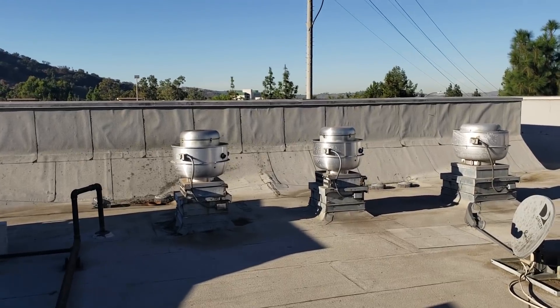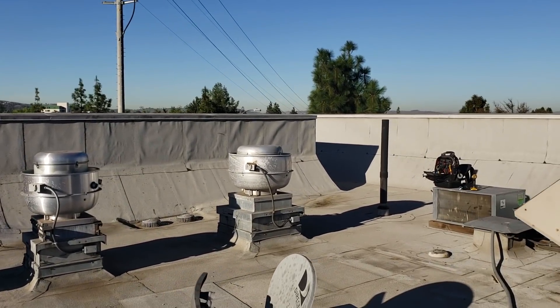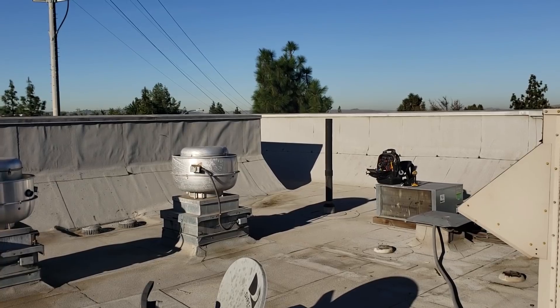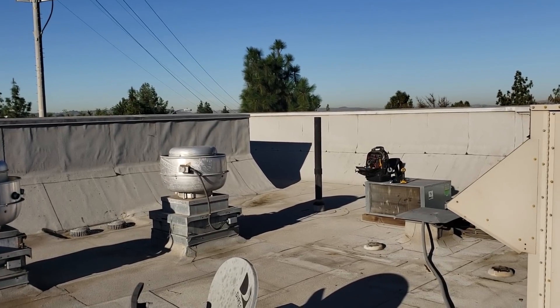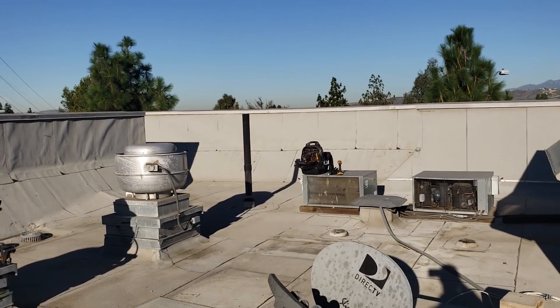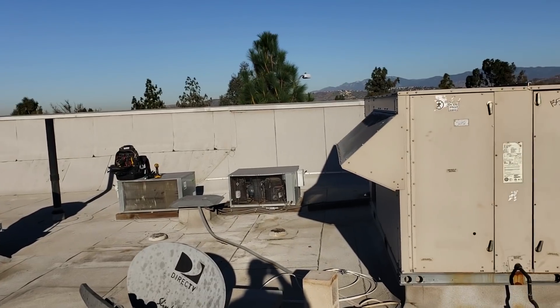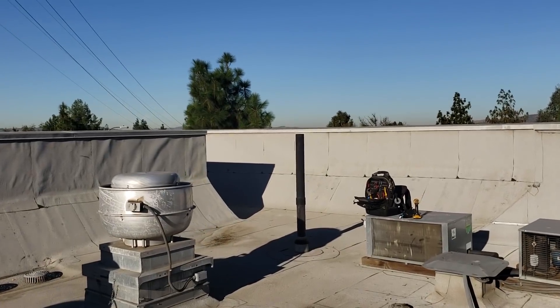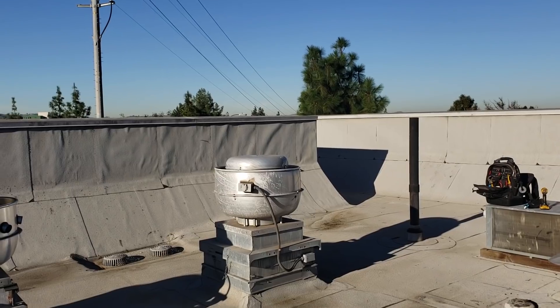That's why this call came out. Interestingly, once I opened up the outside air dampers on the ACs, the vent pipe right there now has sewage smell coming out of it — when I walked up earlier there was no smell. That shows how the negative air pressure was pulling the sewage smell into the building. The customer also needs to consider that the outside air damper on the AC could pull that vent pipe smell in, so they may need to extend or relocate that vent pipe to the other side of the building.